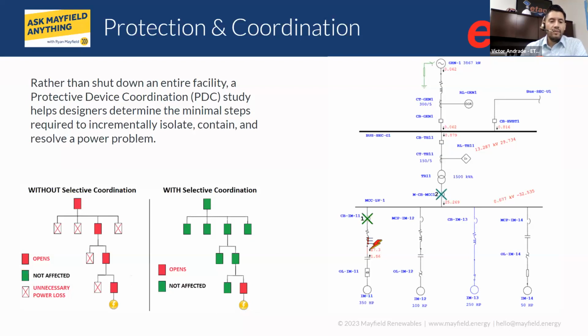Where we want to be is the system on the right-hand side. Again, we're still on the bottom left with selective coordination. So if the study is performed properly and we have an incident, right? Again, the short circuit or the fault happens on the low voltage side all the way to the bottom of the system. It's isolated right at the gear or the switchboard, and the rest of the system remains unaffected in operation. So those are the green locations that you see.